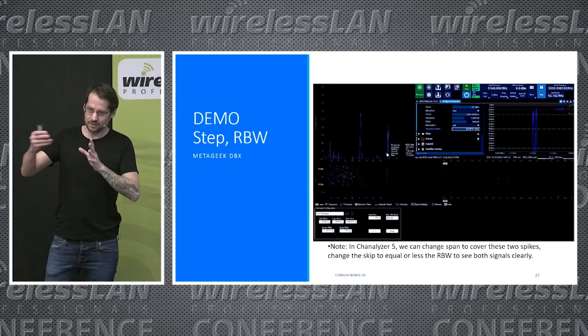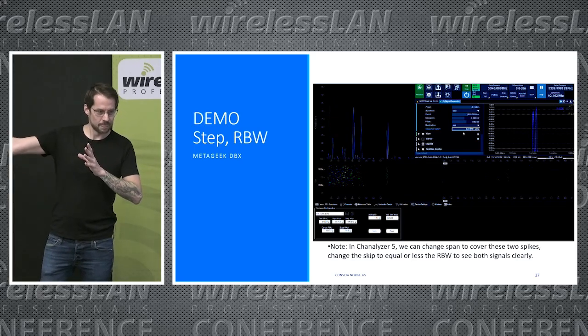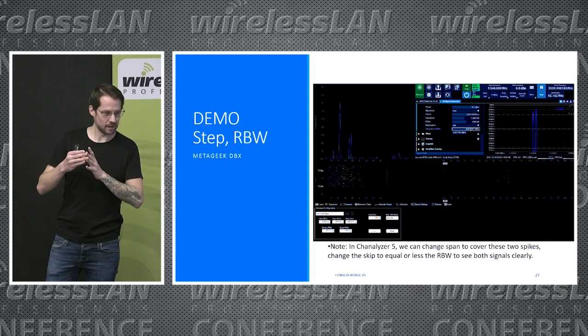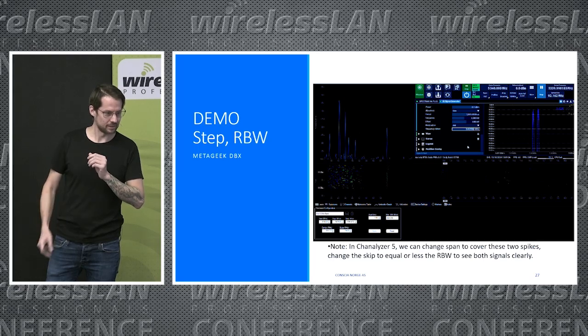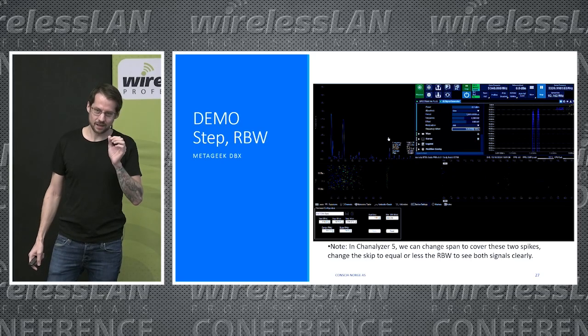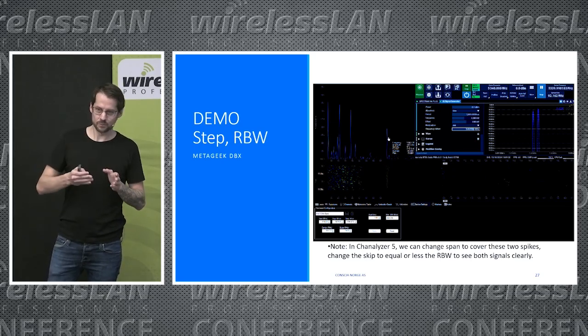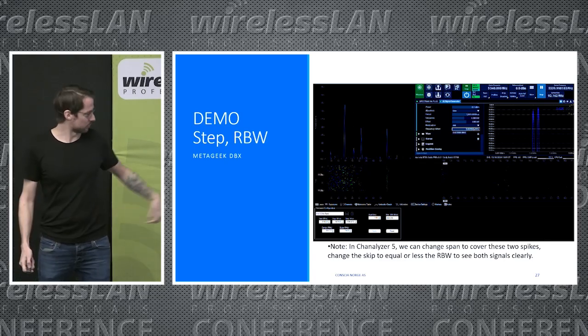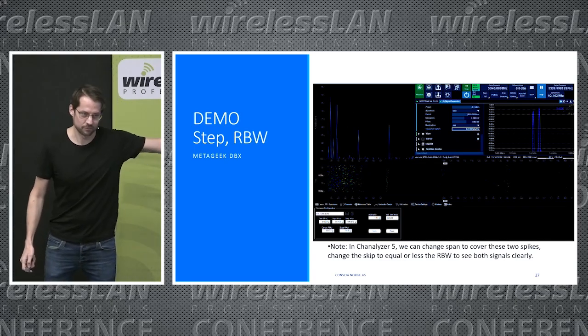So if I can just calculate the step interval, and I move it a little bit further. So I'm doing that. See, I have 3 megahertz apart, so I set it to, let's see, 5, I think now. Yeah. Now it disappears. So if you really can calculate something, you can just put a lot of spikes exactly in between. But you see you can change it below. You have full device settings.